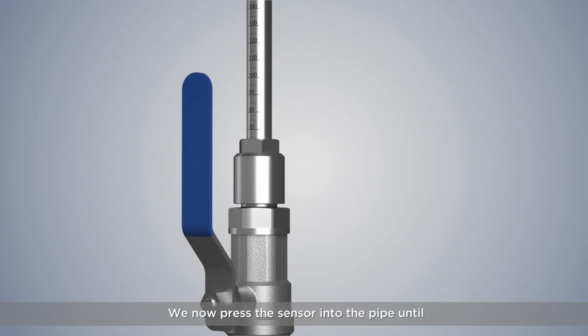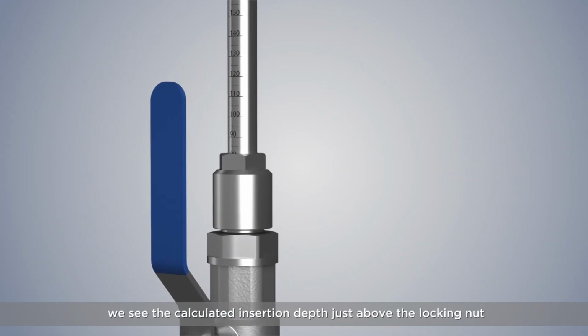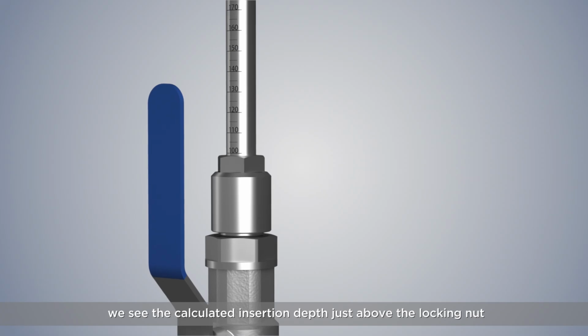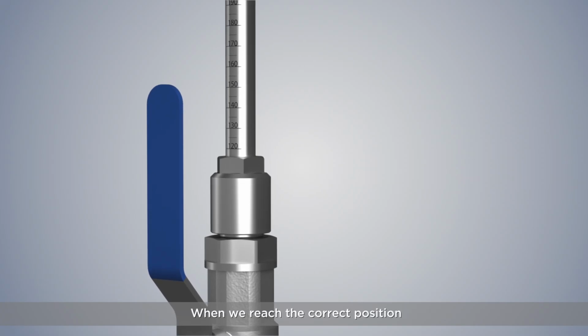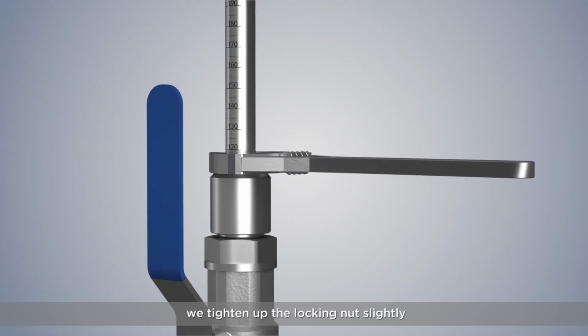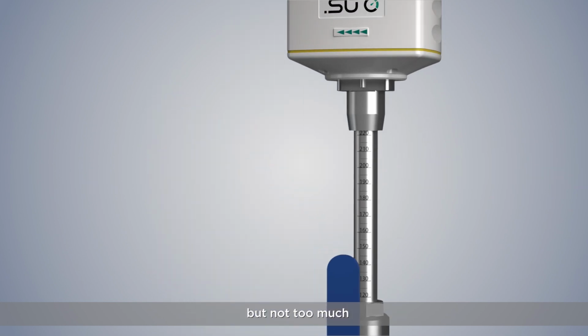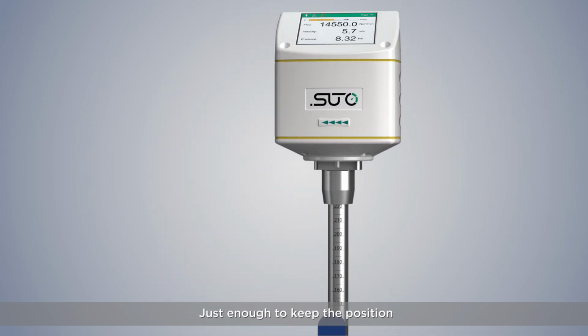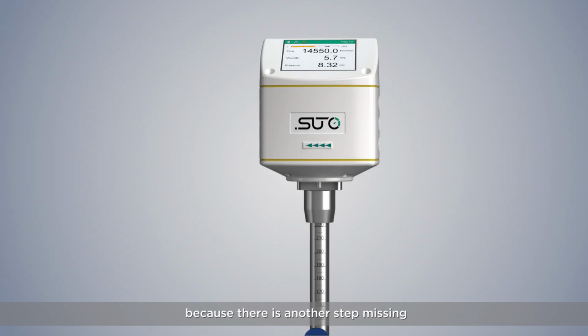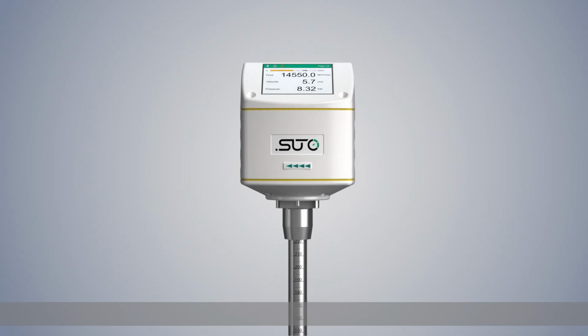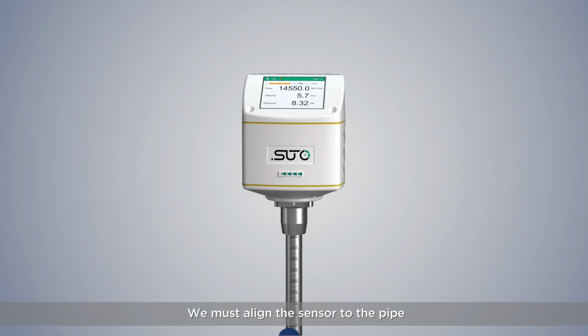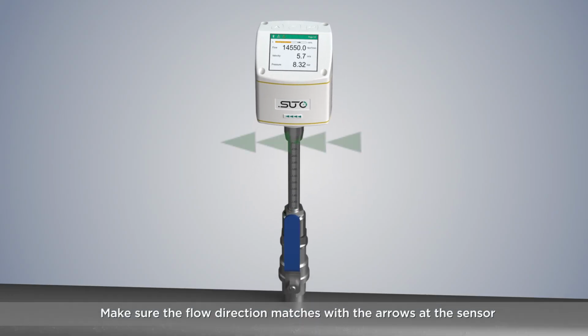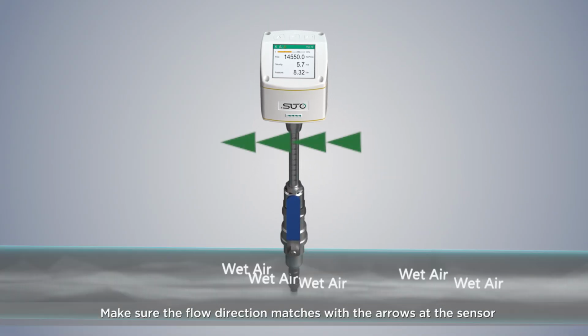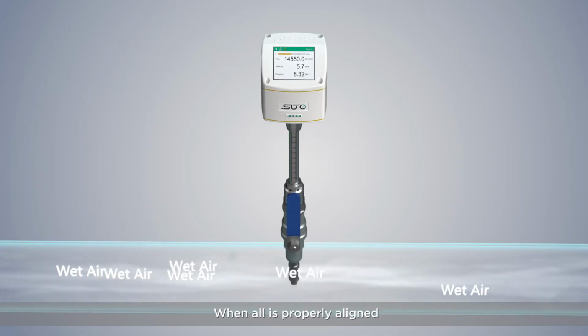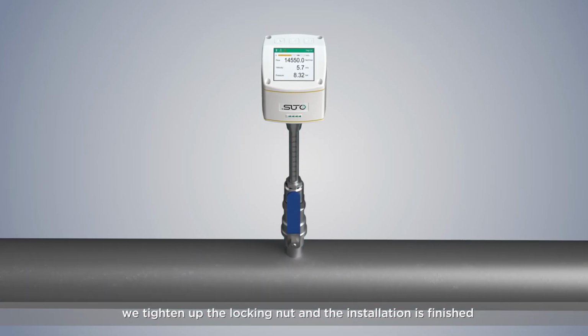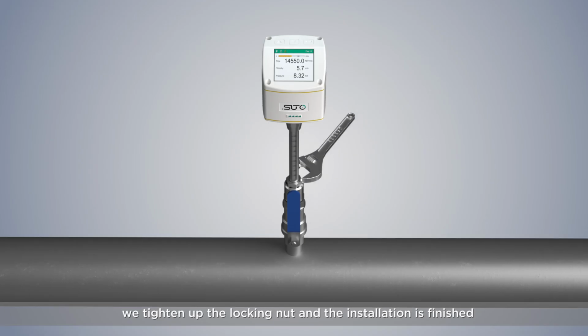We now press the sensor into the pipe until we see the calculated insertion depth just above the locking nut. When we reach the correct position, we tighten up the locking nut slightly, but not too much. Just enough to keep the position, because there's another step missing. We must align the sensor to the pipe. Make sure the flow direction matches up with the arrows at the sensor. When all is properly aligned, we tighten up the locking nut and the installation is finished.